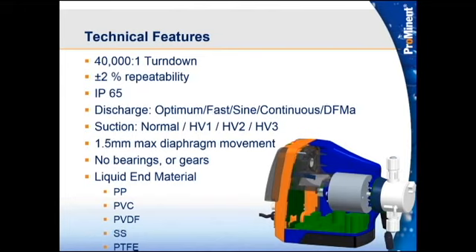Okay, on the stroke length. That's a large turn down. I would feel comfortable saying that this pump could be very repeatable at even a 2,000 to 1 turn down, which is still a huge turn down. Okay. Repeatability is plus or minus 2%. Our pumps are usually more accurate than that. That's just the industry standard for mechanically actuated diaphragm pumps.